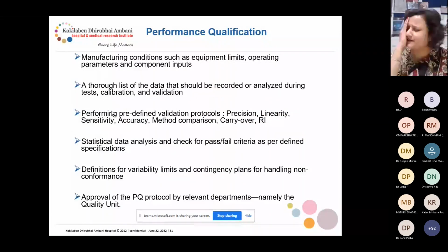But many times during my inspection process, when I used to ask for the performance qualification or verification, the lab director or the biochemistry head used to mention, okay, this has actually been validated or verified by the instrument provider, and the precision, accuracy, everything has been done in their R&D setups. Why do we need to do all those things for performance qualification? We need to check precision, sensitivity, accuracy, linearity, method comparison, carryover, and reference interval.